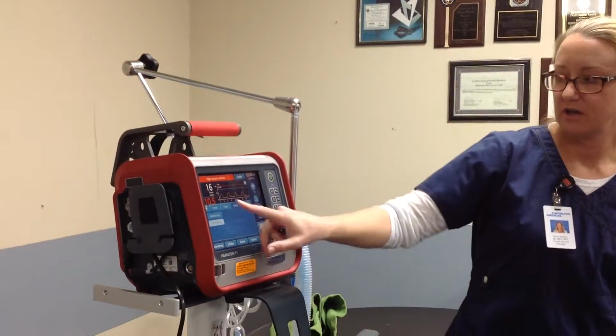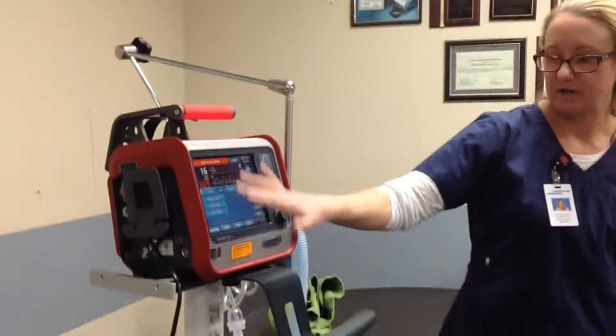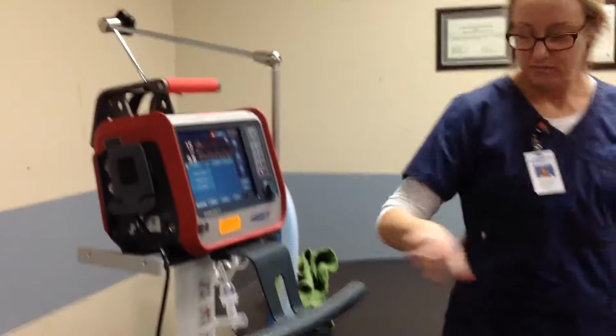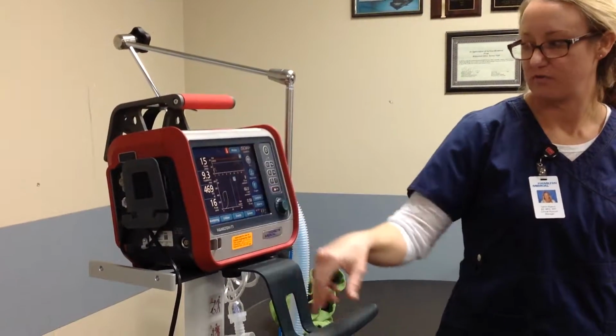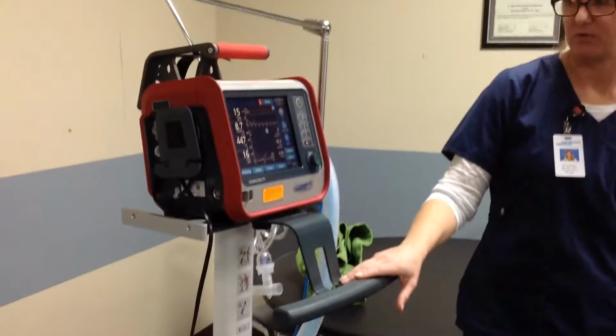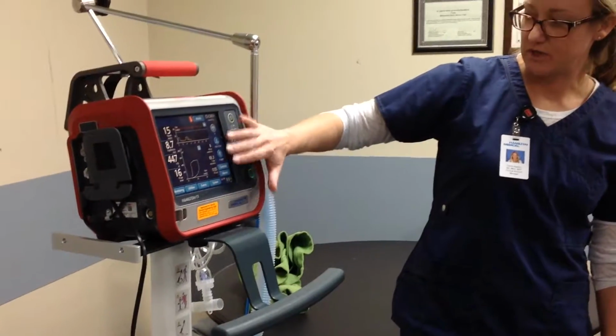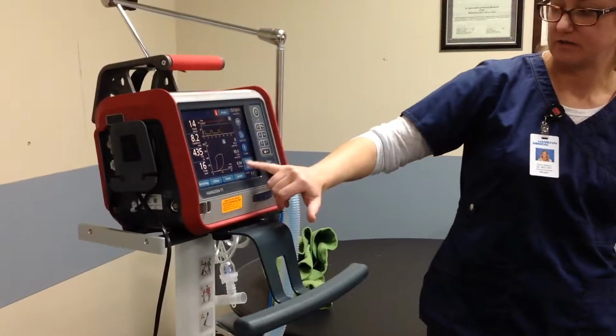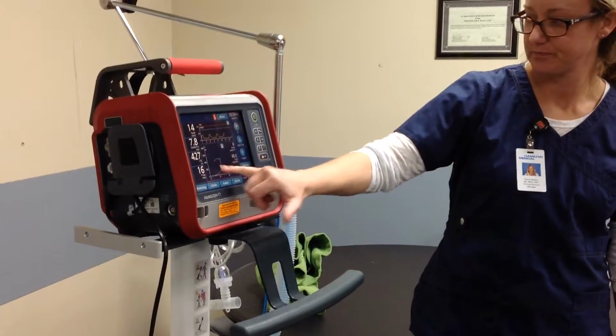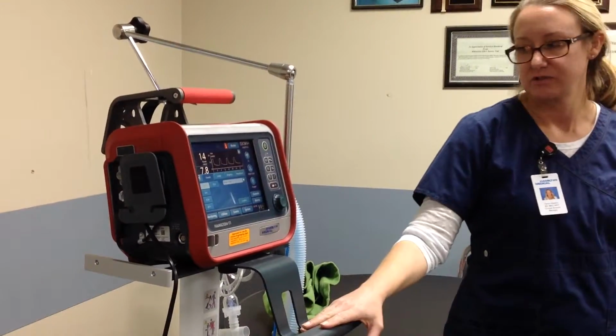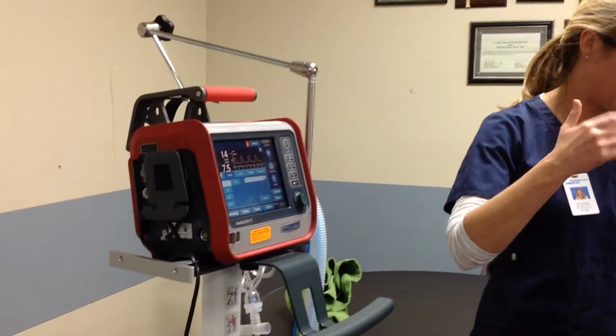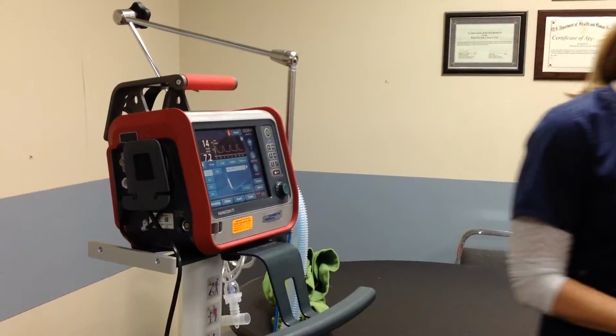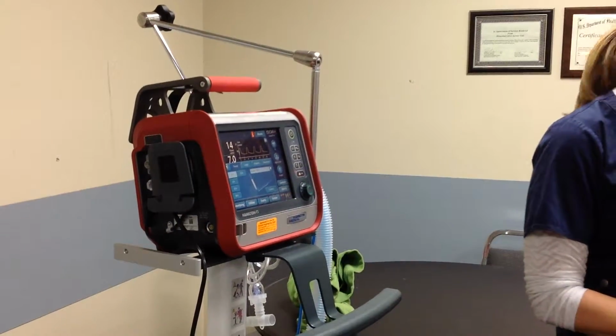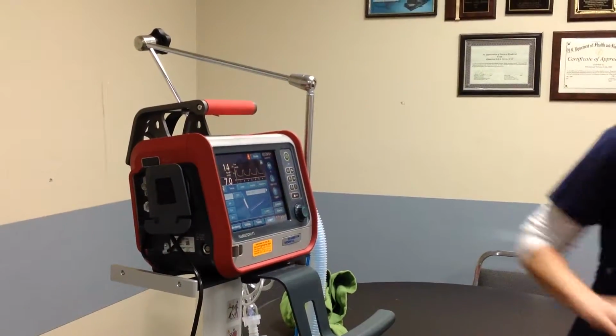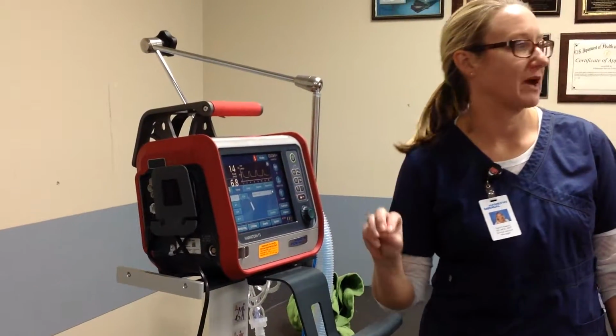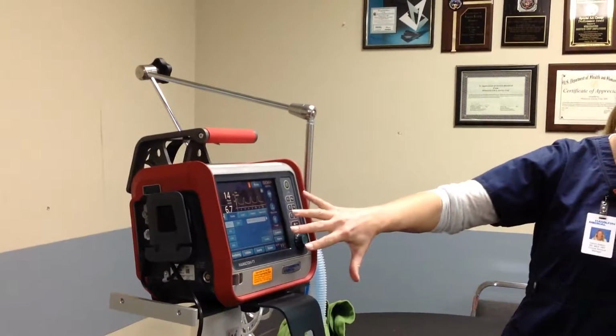If I tap the screen again, I can look at loops. And so if you ever want to get any information about pressure volume information, you can look at a pressure volume loop or a pressure flow loop, and those are available as well. It also tells you their airway resistance, their static compliance, and their exhale time constant on this as well. Tap it again and you can trend. So if you were wanting to trend their static compliance and their airway resistance maybe. It's always trending all of this information. It's just a matter of if you want to access this graphic and look at it.